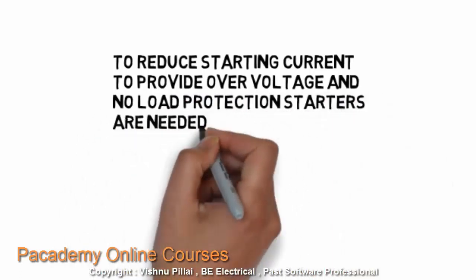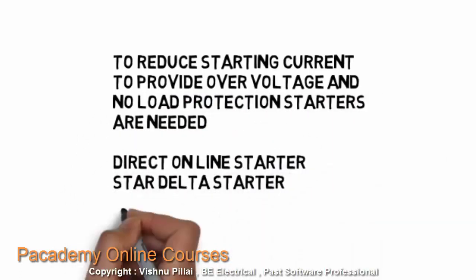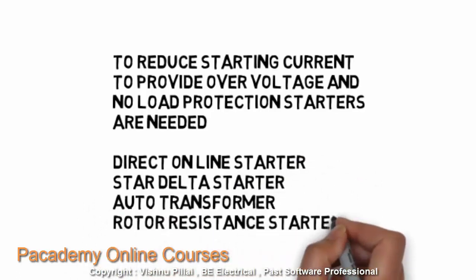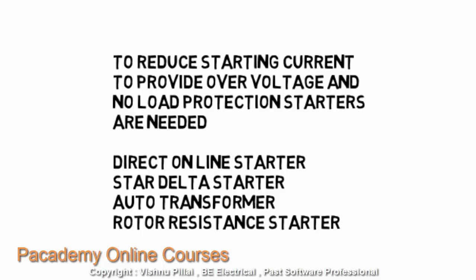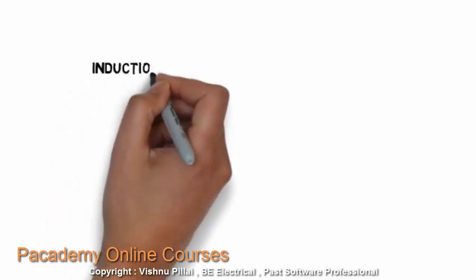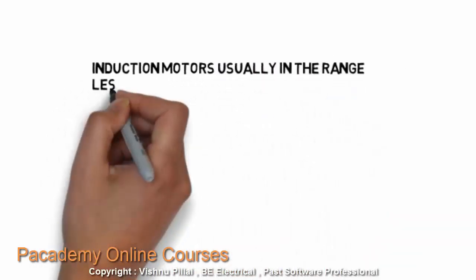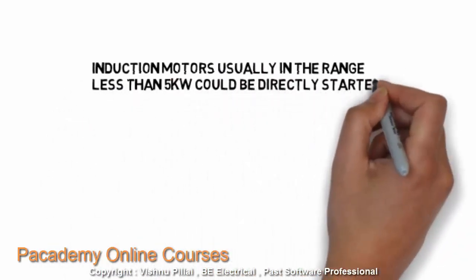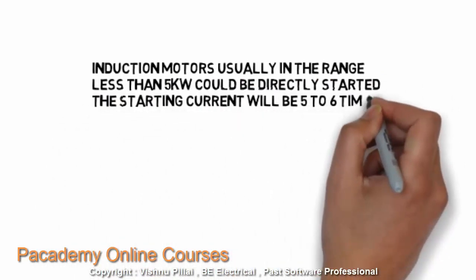To reduce the starting current and to provide over-voltage and no-voltage protection, starters are needed. The different kinds of starters available for the induction motor include: a direct online starter, which connects the motor directly to the supply without any other arrangement; a star-delta starter, which connects the motor in star during starting and delta while running; an auto-transformer to supply reduced voltage at starting; and resistance added to the circuit at the time of starting.